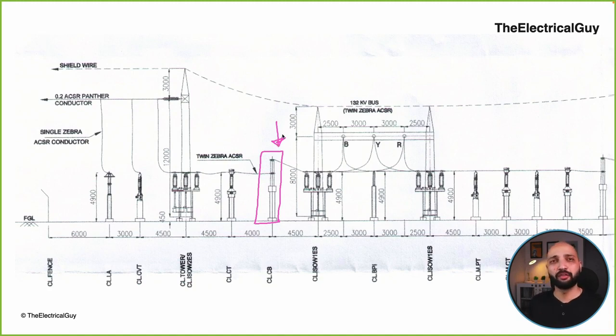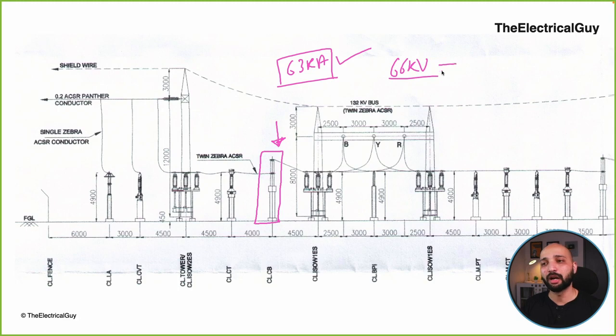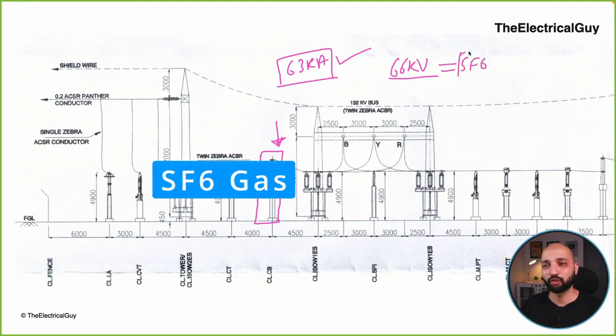Now the biggest difference between a regular switch and a circuit breaker is that a circuit breaker is capable of opening huge short circuit current which can go up to 63 kilo ampere, and which is huge. Circuit breakers are capable of breaking this current as well. It has an insulating medium which helps in quenching the arc. So that is a circuit breaker. Now always remember, all the circuit breakers of 66 kV and above are with SF6 gas as of now.